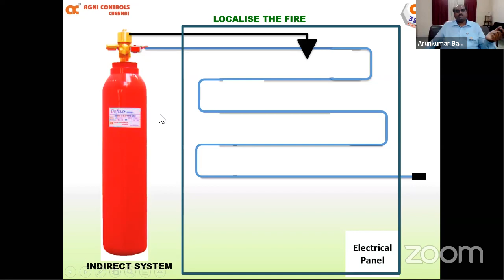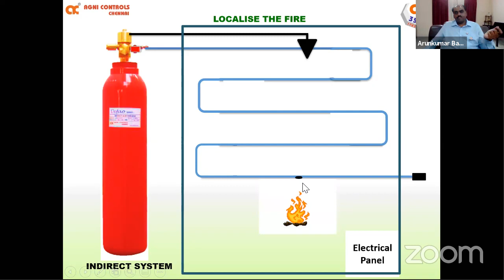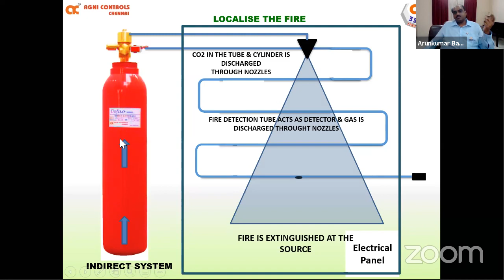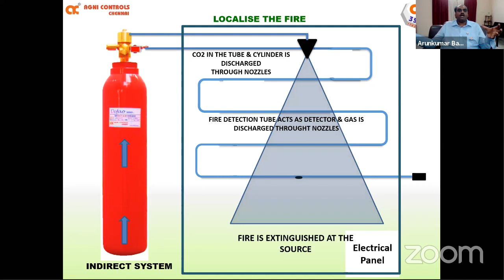I'm going to introduce a fire again. Once I introduce a fire here, this detection tube will operate, and once it operates, the contents from the cylinder will directly go through this tube or pipe and discharge from the nozzle. The difference here is the contents discharge from the nozzle, and if we have multiple nozzles, we can cover much larger space and bring an inert atmosphere for a larger volume.